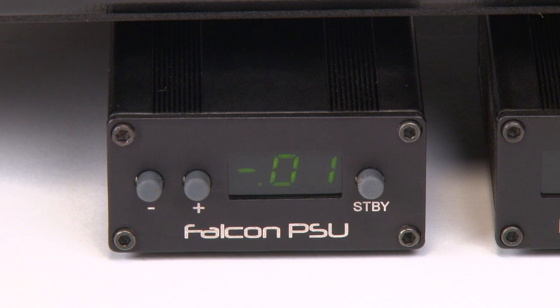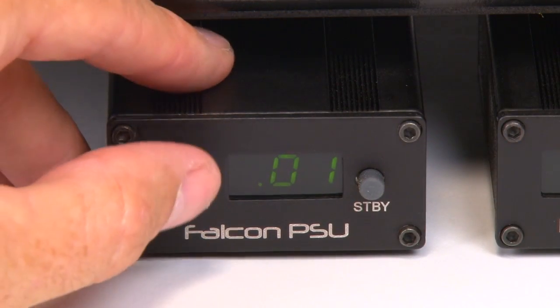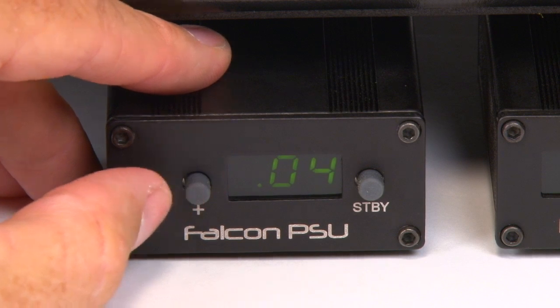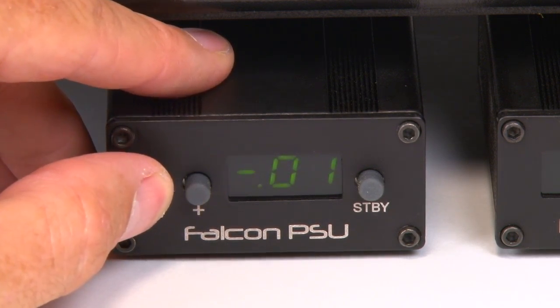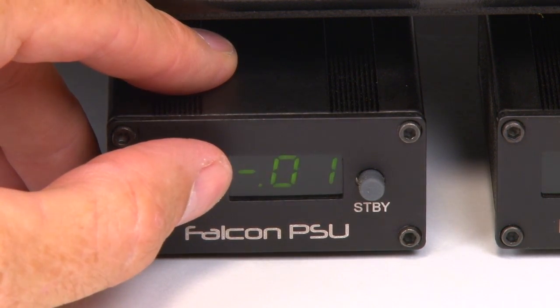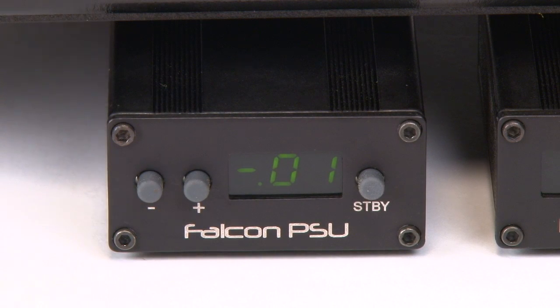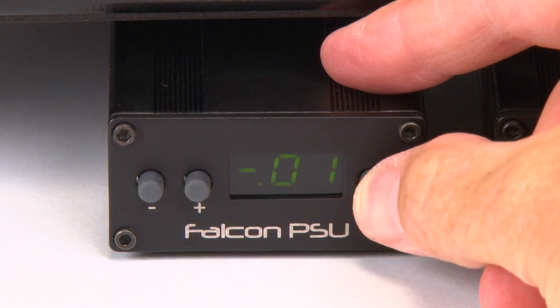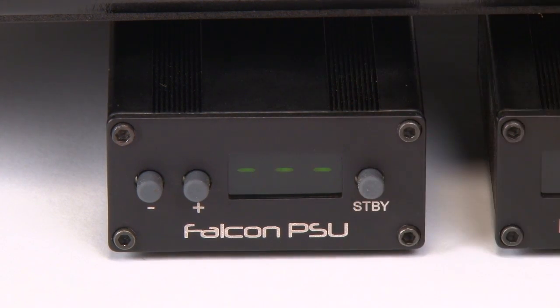To select the other speed, press and release the standby button. Adjust the speed for the new selection as before. When both speeds are properly adjusted, save the calibration data by pressing and holding the standby button. The display will show SAV indicating the data is stored, then revert to standby mode.